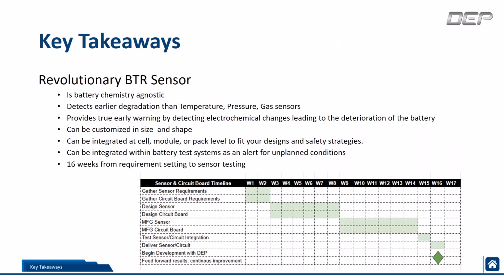So, the main things to take away from this sensor. Because this doesn't work like the traditional sensors already in existence, it's not focused on any one type of gas. It's actually focused on the chemical changes happening inside the cell as its main base point. And so because of this, it's completely chemistry agnostic. It detects earlier than any of these other sensors already in existence: thermocouples, pressure, gas sensors. It provides a true early warning by detecting those electrochemical changes leading to the deterioration of the battery.